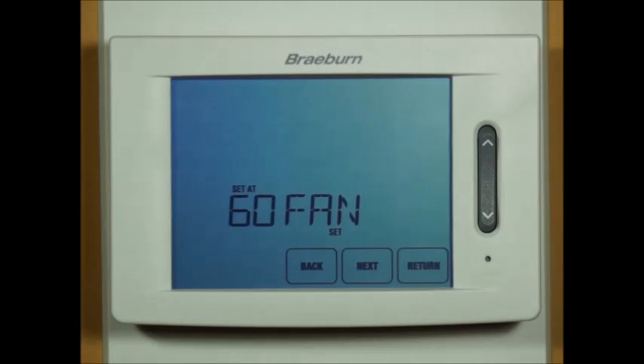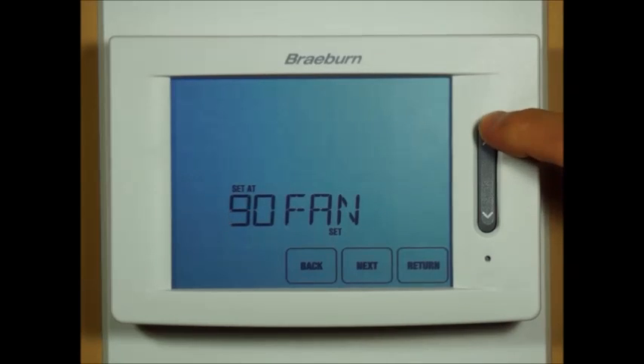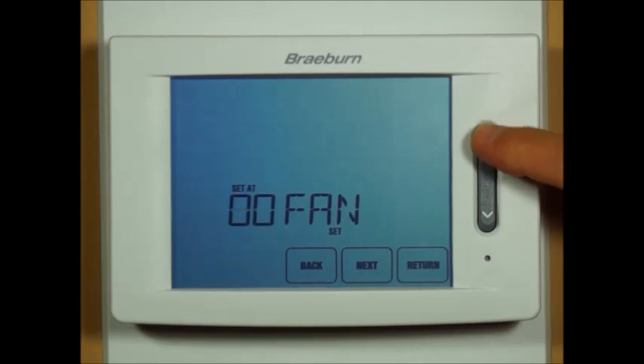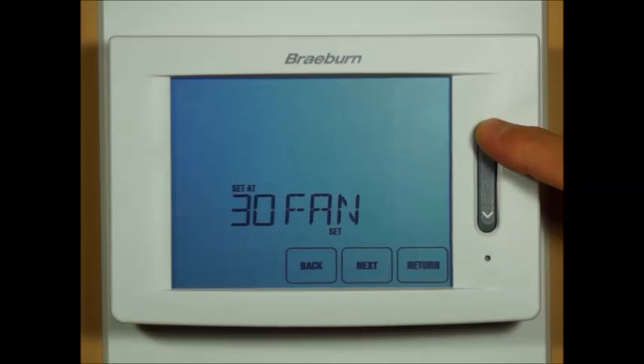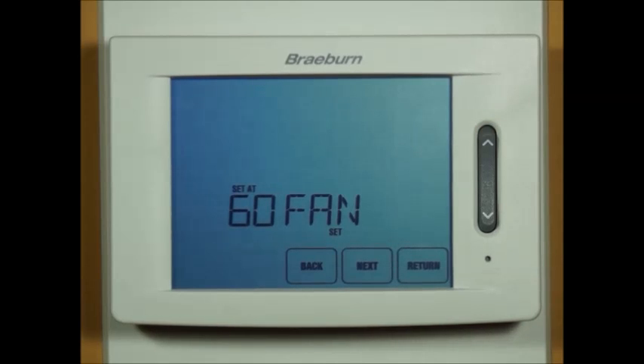Residual cooling fan delay gives you a 60 second, 90 second, zero second, or 30 second delay in cooling mode after the compressors have shut off during which the fan will continue to run.